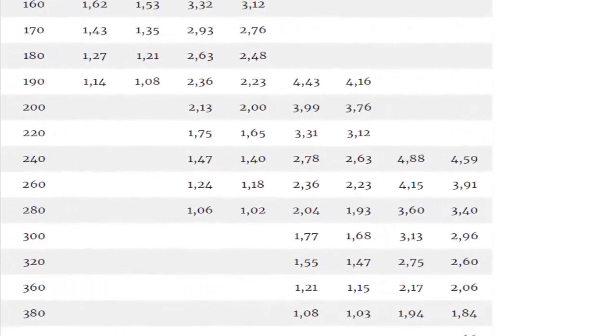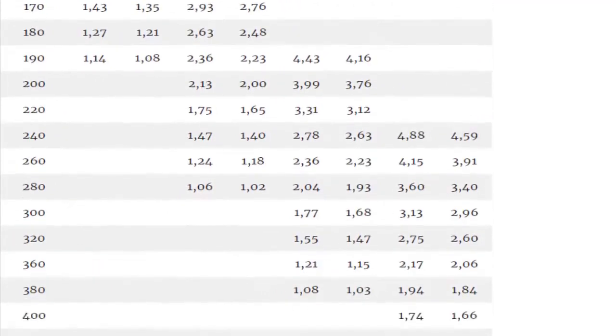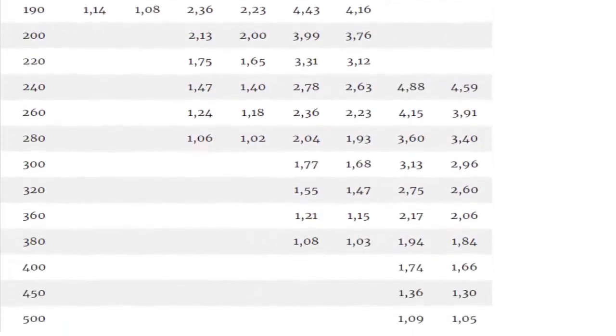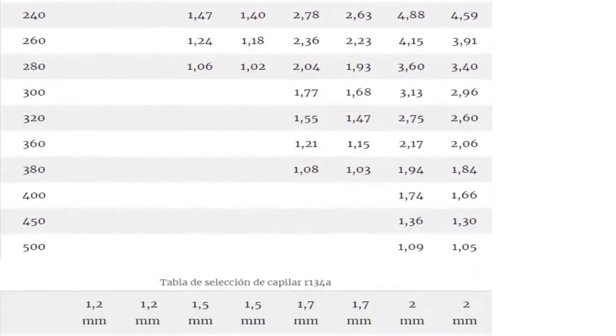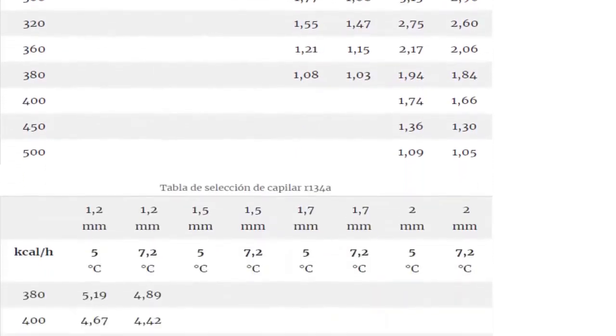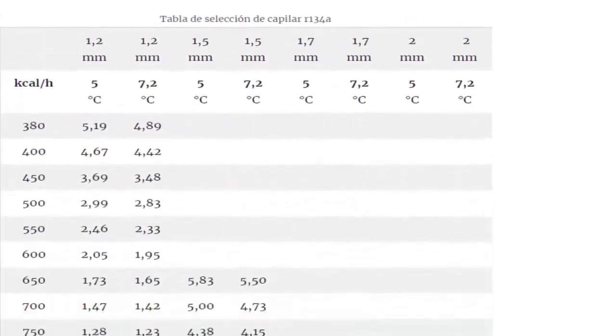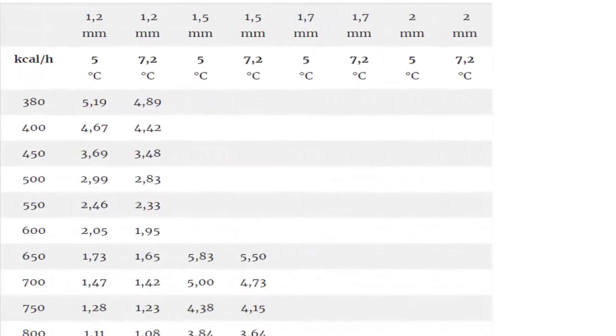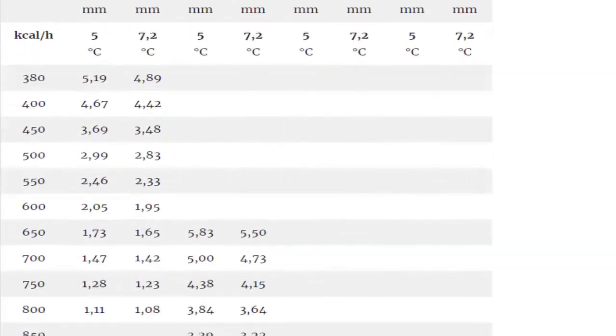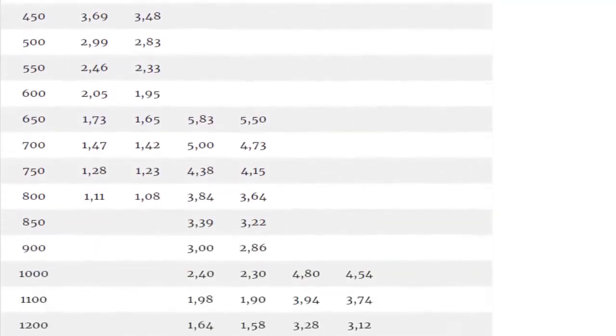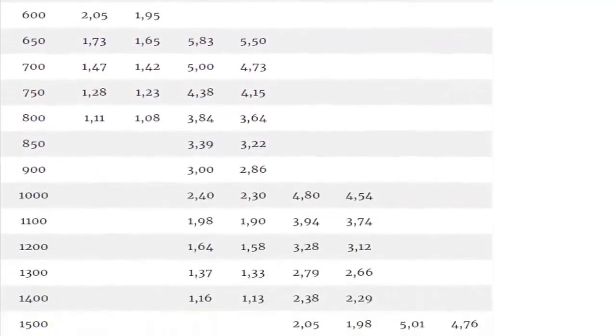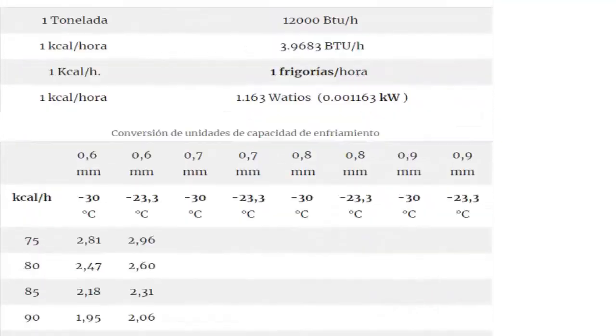7. A percentage change in capillary diameter can change the flow of refrigerant to the evaporator more than an equal change in capillary tube length. 8. However, the restriction offered by the capillary can also be changed by lengthening or shortening the tube, using this method for final calibration.